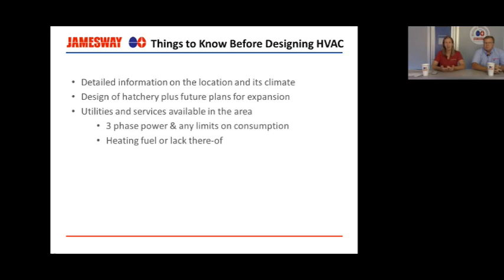The other thing that can be important, and we have had some customers have issues here, is what utilities and services are available in your area. Not every hatchery in North America has three-phase power, and that actually limits the kind of equipment that I can select in your HVAC design. Also, if there's any limits on consumption, you may only be able to get so much gas per month or so much electricity per month. We've seen that issue in Russia before.